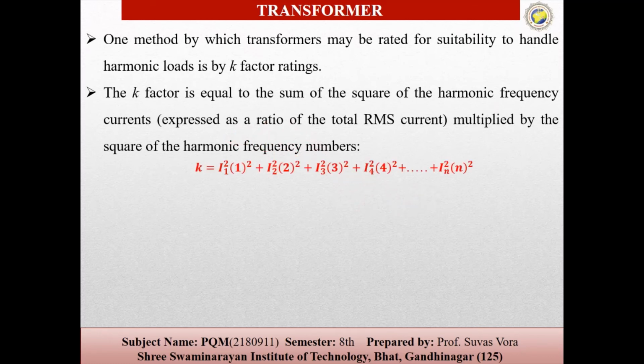सो इक्वेशन इज K इक्वल टू ये जो करंट है I1 स्क्वायर, देन I2 स्क्वायर, देन I3 स्क्वायर एंड I4 स्क्वायर, एंड द 1 2 3 आर द मल्टीपल ऑफ द स्क्वायर ऑफ द हार्मोनिक फ्रीक्वेंसी. ये फ्रीक्वेंसी फर्स्ट फ्रीक्वेंसी, सेकंड, थर्ड, फोर्थ. सो हियर द K फैक्टर इज द IEEE स्टैंडर्ड कोड इज C57.110 standard, and this one is recommended for the setting up of the transformer capacity and provides the equations for the derating of the transformer.